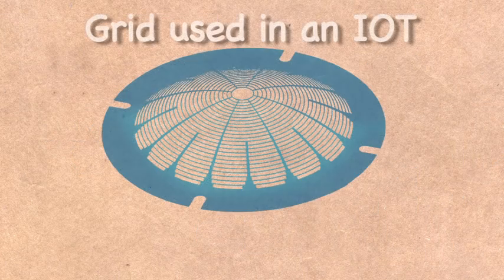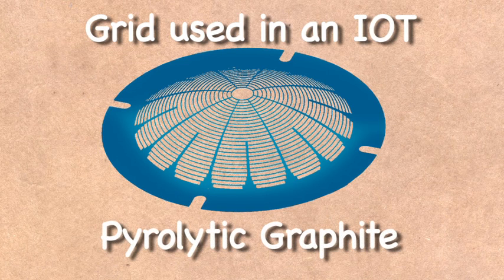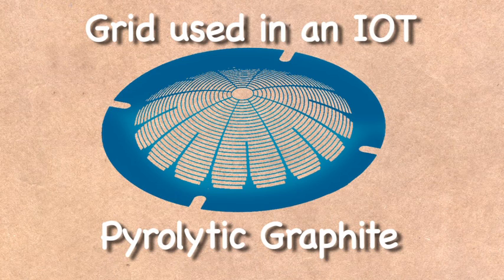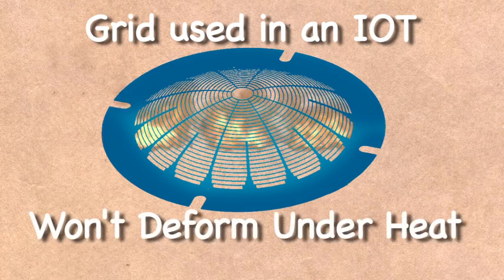The actual grid is made of pyrolytic graphite. It is shaped to fit the concave cathode and is mounted very close to it, about 0.01 mm in fact. The pyrolytic graphite conducts like copper, but can handle the heat of the cathode without deforming.